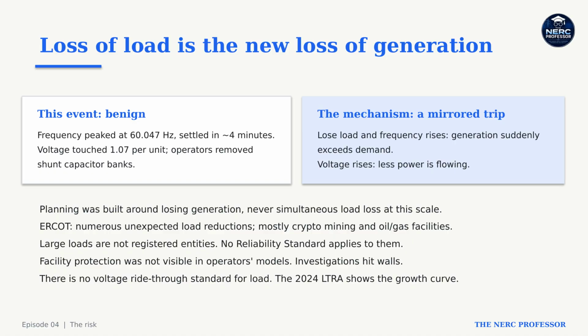Here's the thing, losing 1500 megawatts of load looks like losing 1500 megawatts of generation mirrored. Frequency rises because generation suddenly exceeds demand. Voltage rises because less power is flowing. This event stayed benign. Frequency peaked at 60.047 Hz. Voltage touched 1.07 per unit, and operators pulled shunt capacitor banks to bring it back down. Fine, but watch this. Our planning framework was built around losing generation.